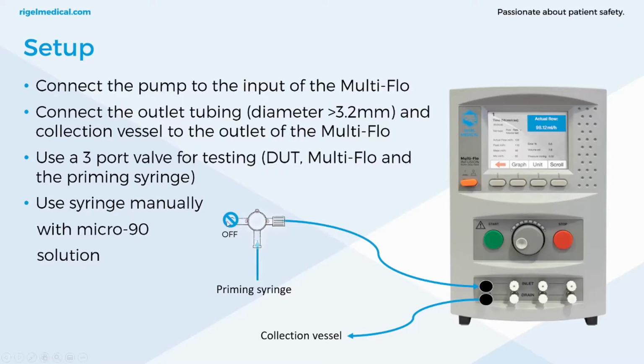So we'd have our device under test here, our infusion device, but for the first part we're just going to turn this off. And the reason we don't just switch between tubing is this is how we can introduce air or contaminants into the system. So when we're priming, we ideally want this set up where we can switch off using the valve while not having to introduce any new tube into the system.